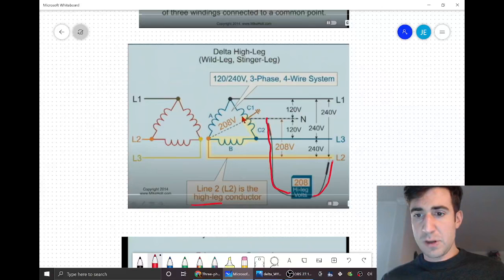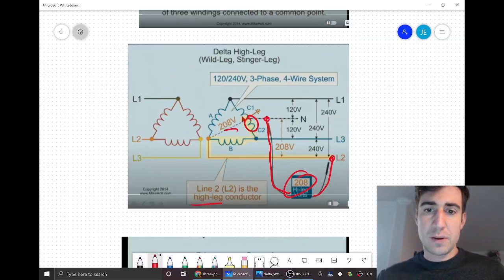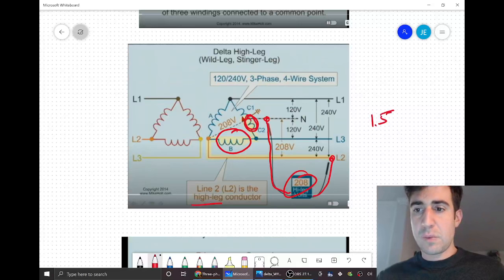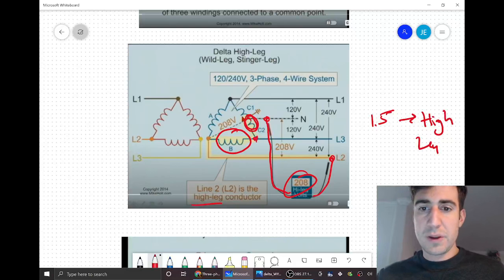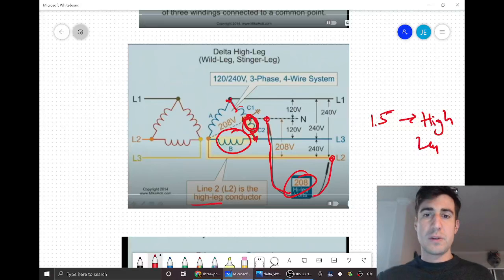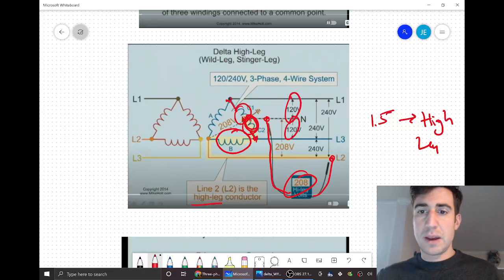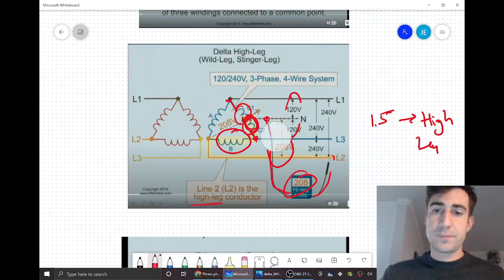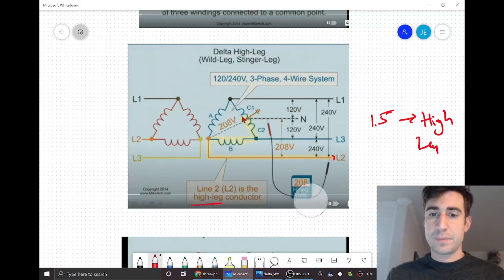This is a multimeter between line 2 and the neutral. So why is this 208? Why is that the high leg? Well, because we have one full winding and a half. 1.5 windings, that will be your high leg. We can see from line 3 to neutral, we just have a half, as well as from 1 to neutral, we also have a half. So this is 120, 120, and then the 1.5 yields 208. Something to consider.